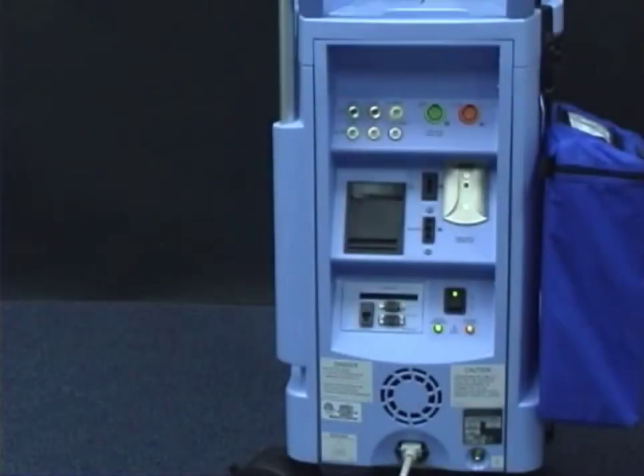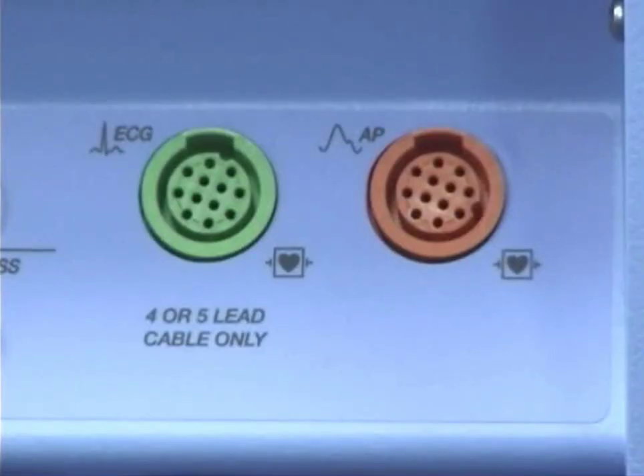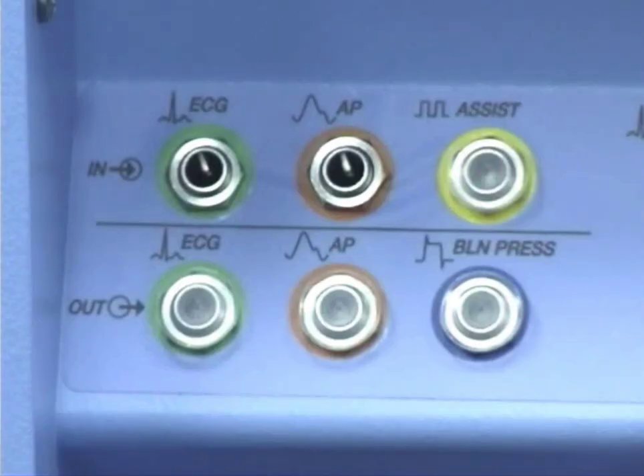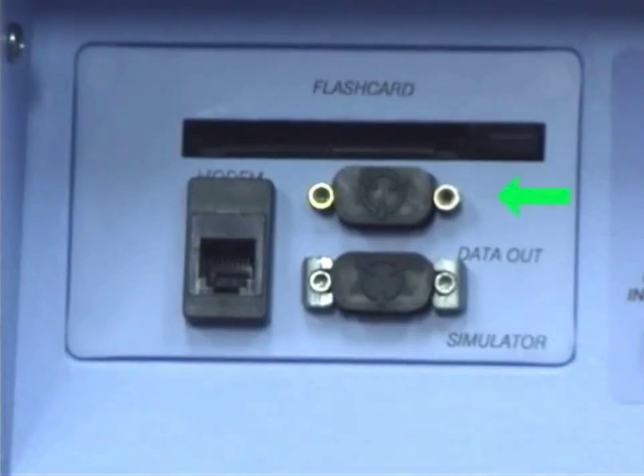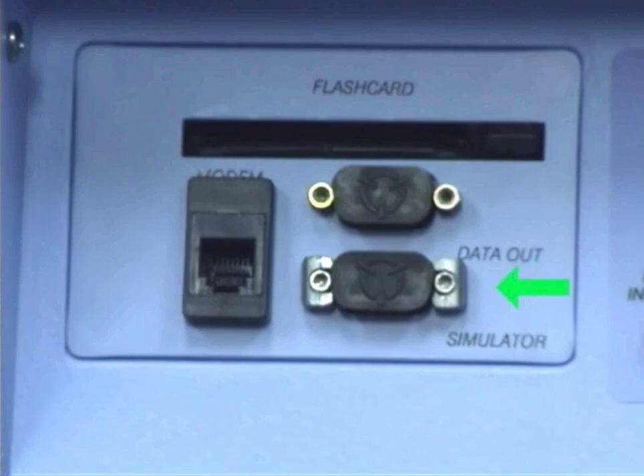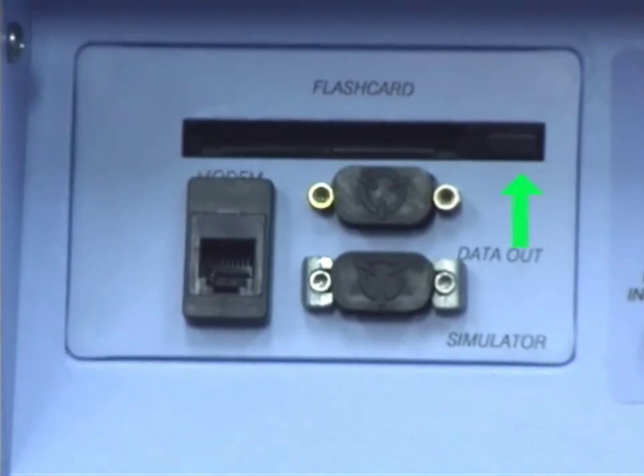The front of the console contains all of the patient input and output connections, as well as an RS-232 data connection for patient data management, a simulator connection, a flash card slot, and a modem for remote troubleshooting.